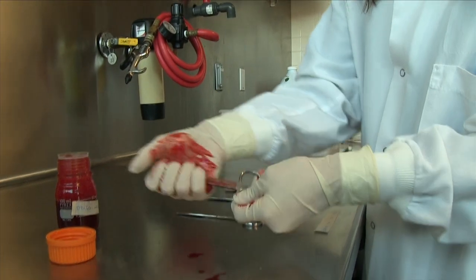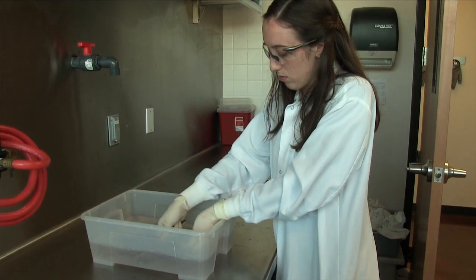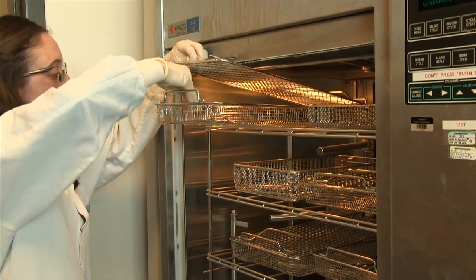Typically, new conditioned devices have been used for these reprocessing validations. However, the FDA is concerned that used conditioned devices be used for these validations in order to determine that during the lifespan of the device, the reprocessing instructions are adequate and can be carried out appropriately. However, used conditioned devices are often not available, as this is a first step for medical device manufacturers to get their product on the market. So the FDA is requesting that manufacturers simulate used condition by taking the device through a series of cycles of contamination, cleaning, and disinfection or sterilization in order to achieve a used condition device.